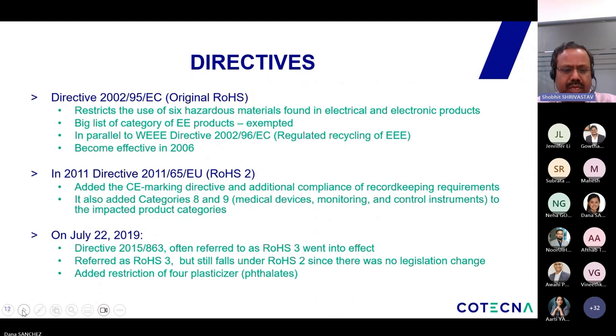So they have introduced the CE marking, and one additional requirement for the manufacturer, importer or distributor in the EU market: to keep the record of whatever compliance they have for the product which they are selling in the EU market. They should keep the record for at least 10 years, and they need to present all these records to the authorities whenever required.